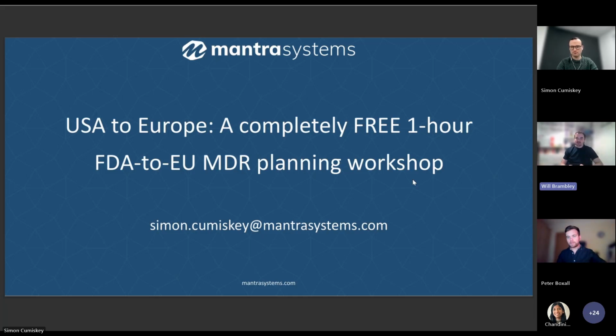Yeah, I think it's one of those frustrating questions where we really have to give a range, but I'll try and be as specific as I can. The cost of overall for a notified body review process can be anything from 30,000 euros up to 150,000 euros. And there's a few things that influence that. The first one is the characteristics of your device, what classification it is, what's the risk class, what do you need to prove, what are your claims?